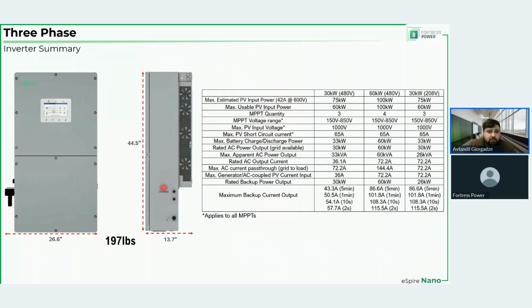For those who are going to be sizing the PV array and the strings for these inverters, it will be very important to know that maximum short circuit current per MPPT is 65 amps. Now, I must remind everyone that each MPPT can accept up to 2 strings. We're going to touch base on that later. So 65 amps is not per string. 65 amps is with 1 or 2 strings. So 2 strings combined should not exceed 65 amps.